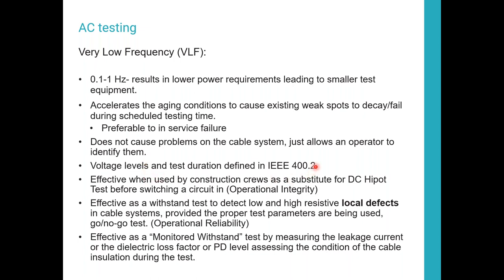There are voltage test levels and durations that are defined by standards. So IEEE, ANSI, and IEC all give you voltage levels to use for testing. So you don't just randomly go in and say, okay, I'm going to put 10 times my voltage on this cable. They define 2, 3, 5 times nominal voltage for X amount of time. If you don't see any breakdown, the cable passes. You can come back in a year or two and retest. So there are definitely standards out there, which we'll talk about a little bit coming up, that identify tests for your different voltage classes.